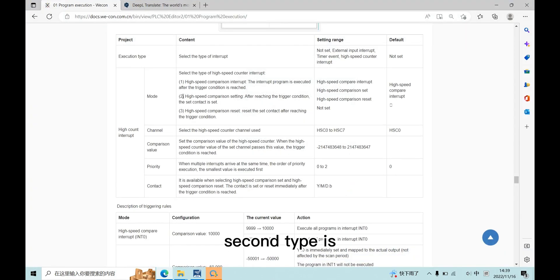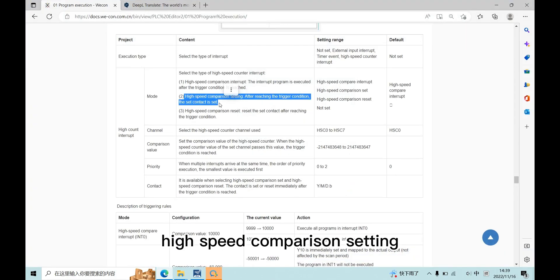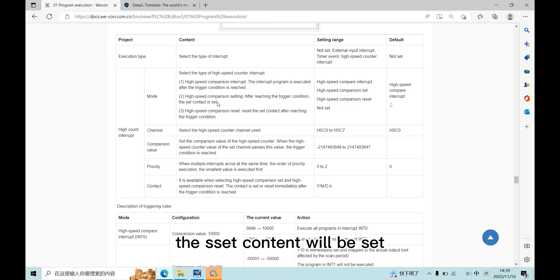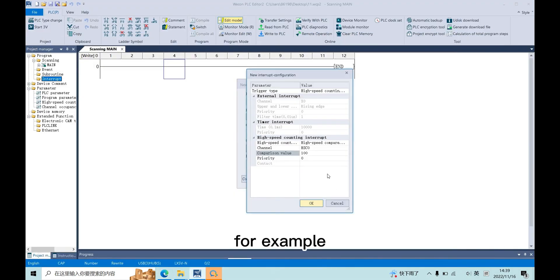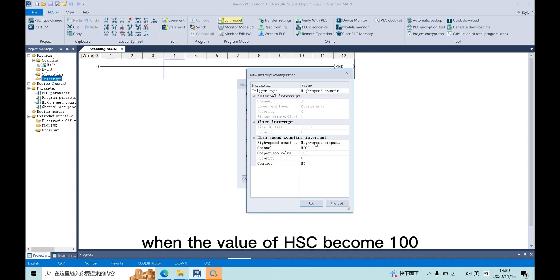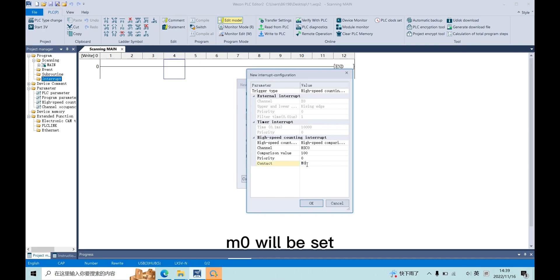The second type is high-speed comparison setting. After reaching the trigger condition, the set content will be set. For example, if we choose this type, when the value of HSC0 becomes 100, M0 will be set.